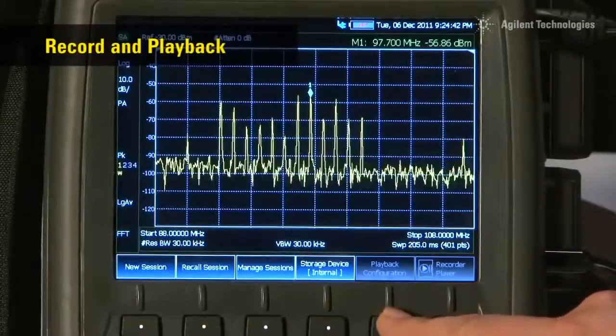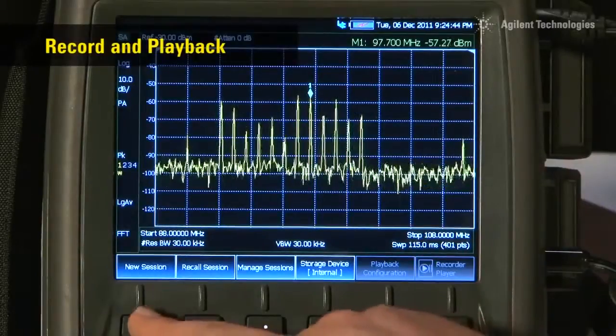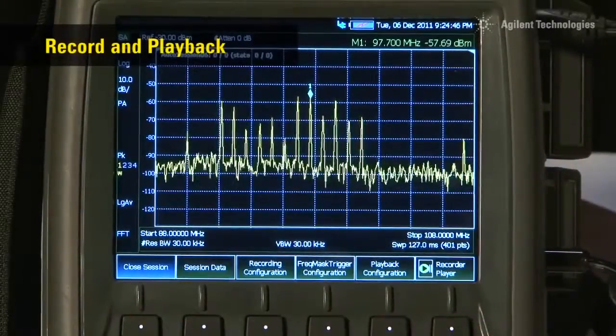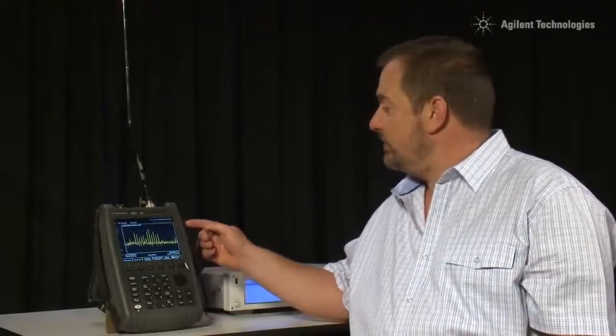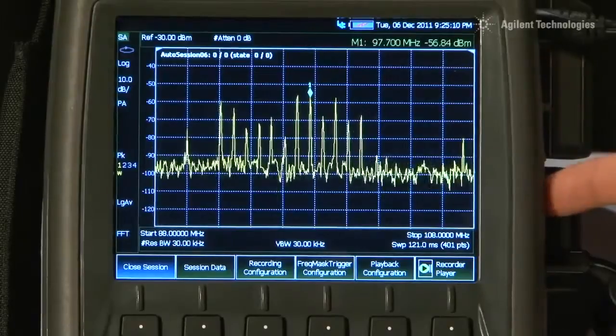You will also see there is a record and playback setup button. Here I can create a new recording session and tell the instrument to record a history of the traces, either to the internal memory or to a USB stick or the Mini SD card.